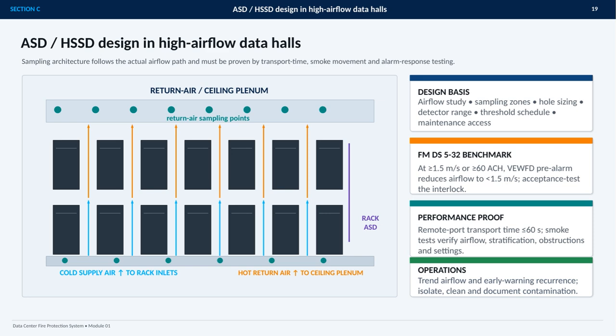The slide also identifies an FM DS 5-32 benchmark for conditions of at least 1.5 meters per second or 60 air changes per hour. In that situation, a very early warning fire detector pre-alarm is intended to reduce airflow below 1.5 meters per second, and the interlock must be acceptance tested. Performance testing then verifies remote port transport time of no more than 60 seconds, along with smoke movement, stratification, obstructions, and detector settings. Finally, operations should trend airflow and recurring early warnings, while contamination is isolated, cleaned, and documented.